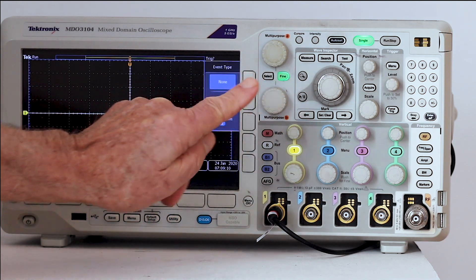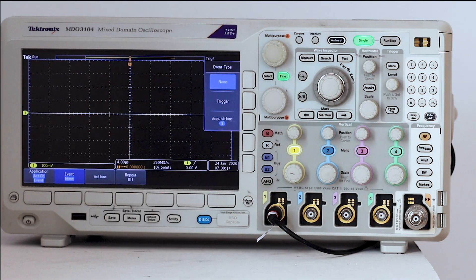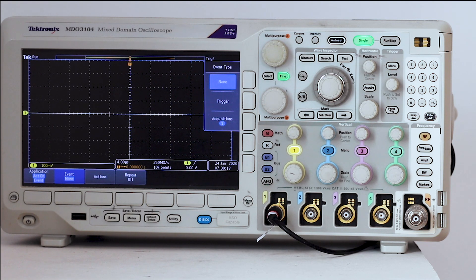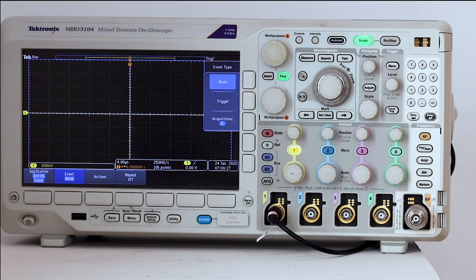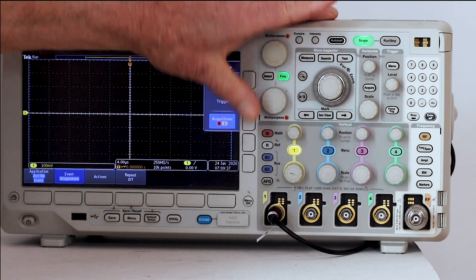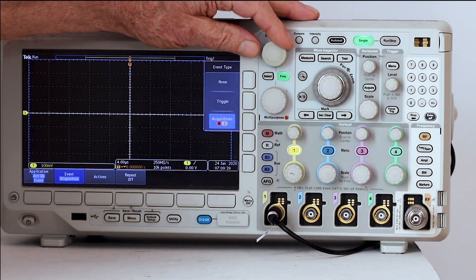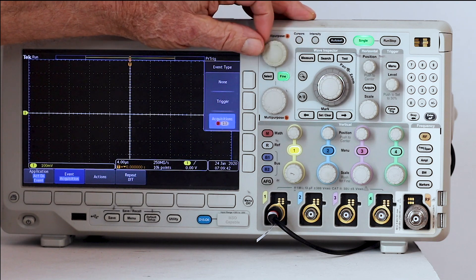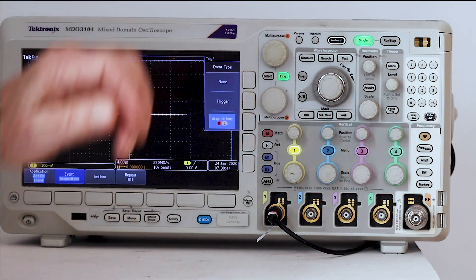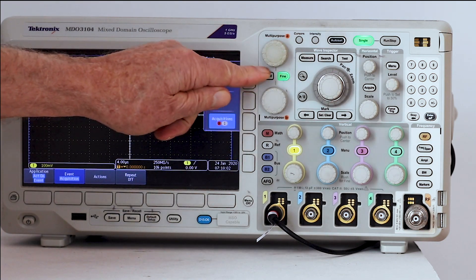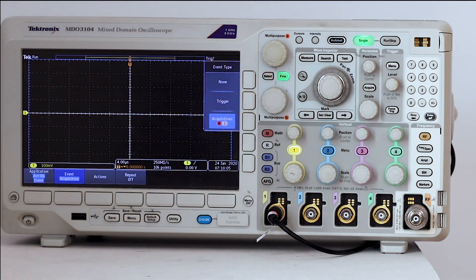The soft key associated with acquisitions in the vertical menu, moreover, toggles this choice off and on in conjunction with the first and second soft keys. When acquisitions is activated, multipurpose knob A chooses the number of acquisitions to comprise an event. Since they range from one to a million, the Fine button under multipurpose knob A should be pressed if necessary to disable Fine. It is always quicker to use the number pad.